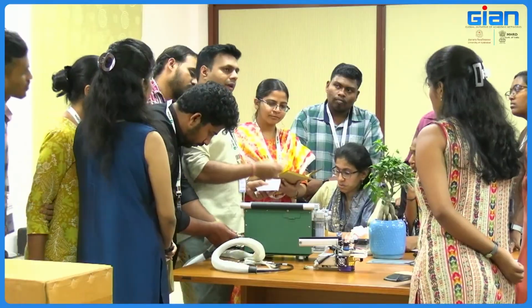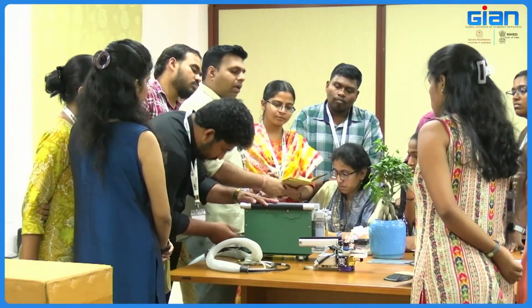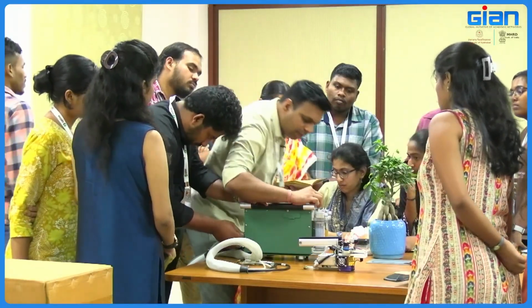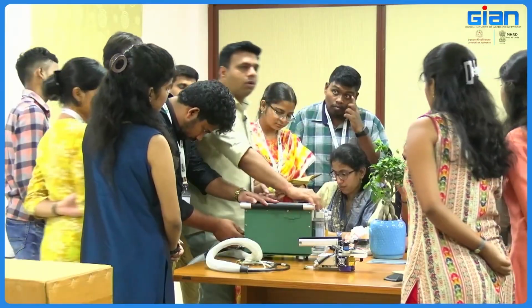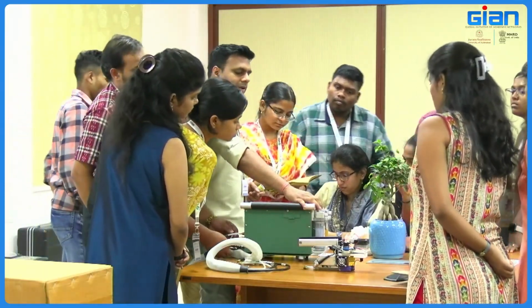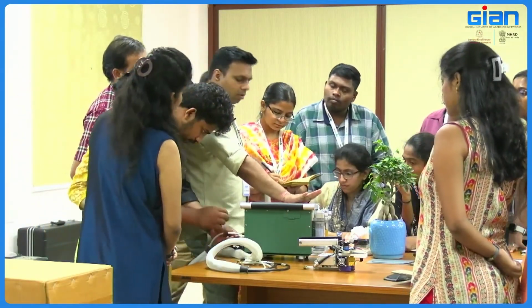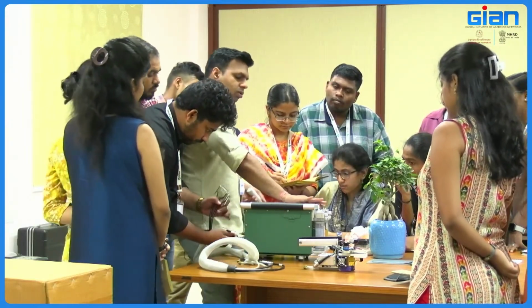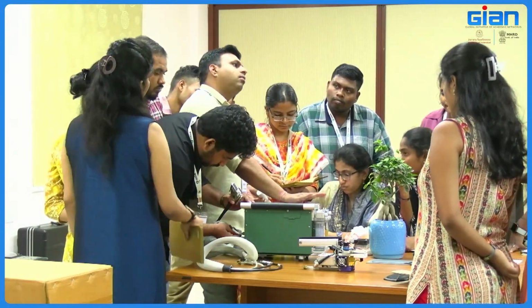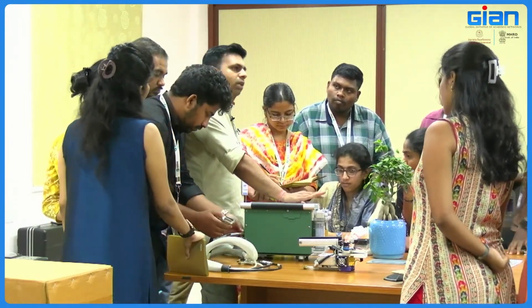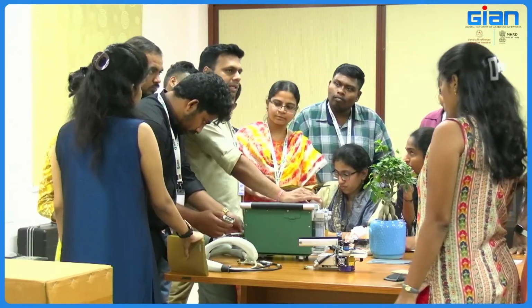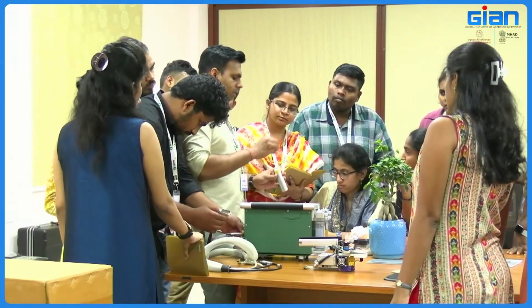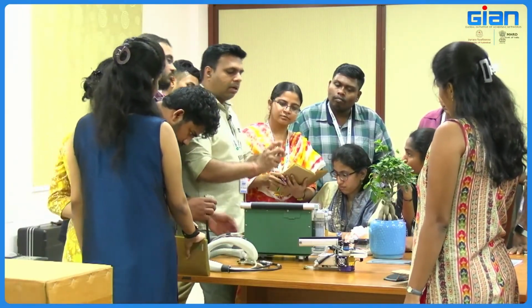Typically after every 4 to 5 readings, you have to change the gasket. It's not damaged, so you can just see physically whether the gasket is damaged or not. I replaced it recently, so it is not damaged, but typically after 5 to 6 readings, or even 2 to 3 days, you have to change the gaskets. So you just put it inside.